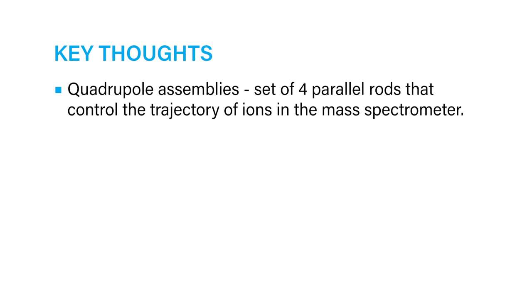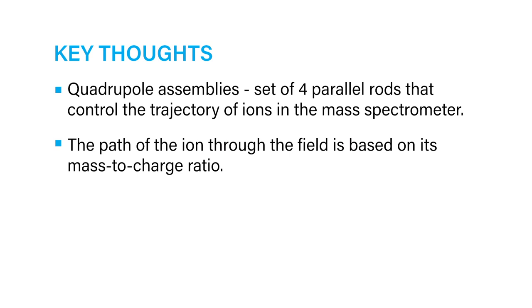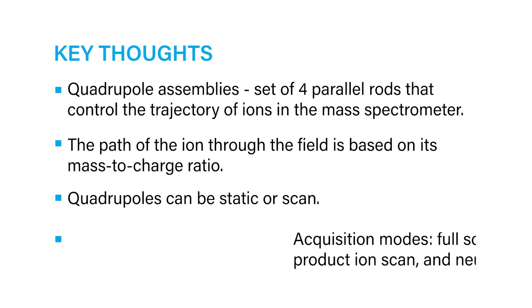A fluctuating field is generated inside the quadrupole by applying RF and DC voltages to the quadrupole rods. The path of the ion through the field is based upon its mass-to-charge ratio. Quadrupoles can be static, where the RF and DC settings are optimized to transmit only the mass-to-charge ratio of interest, allowing only those ions through the mass spectrometer.